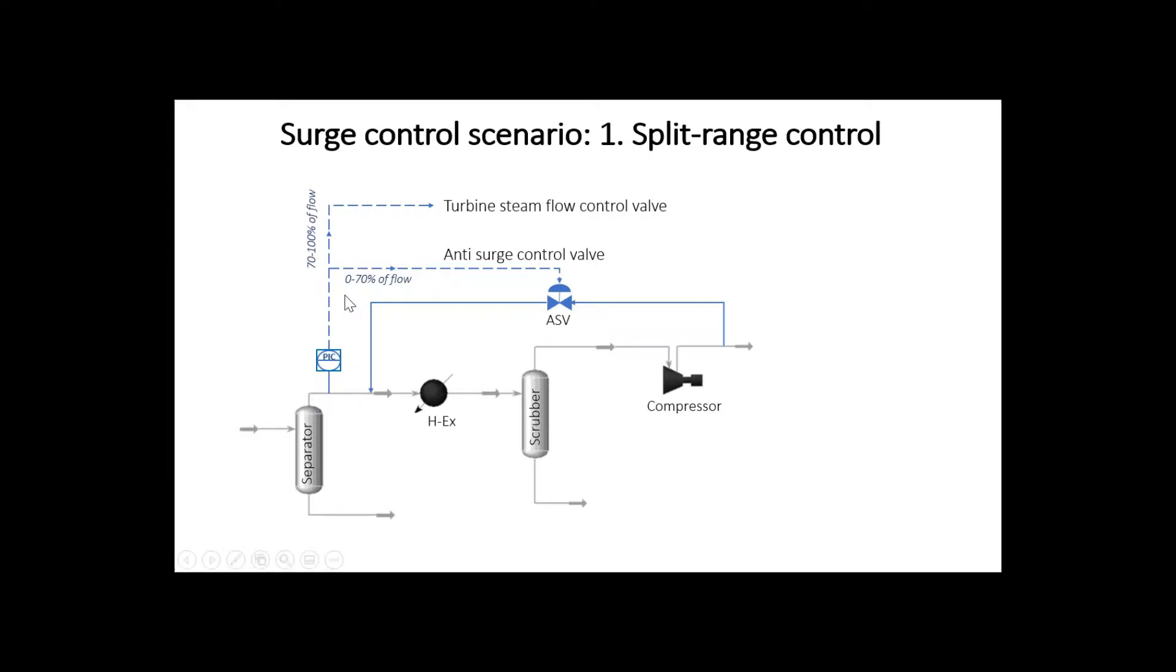Here we can see split signals. To some point, for example, in this case till 70% of flow decrease, the control system changes the compressor speed. Here in order to do so, it decreases the steam flow rate to the compressor turbine.